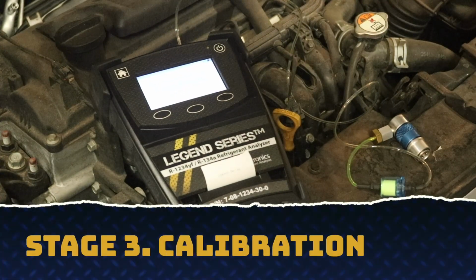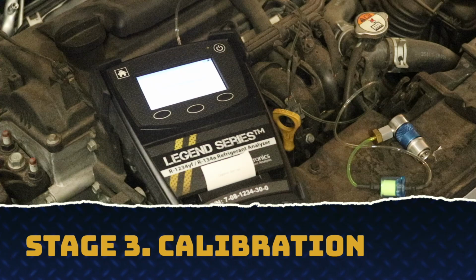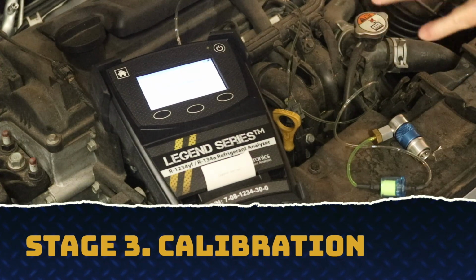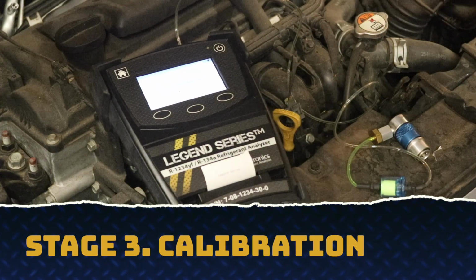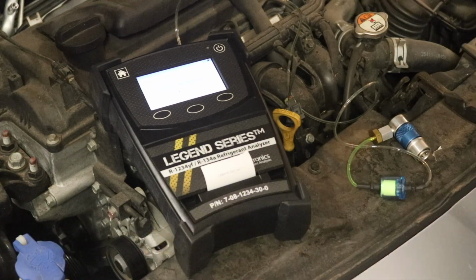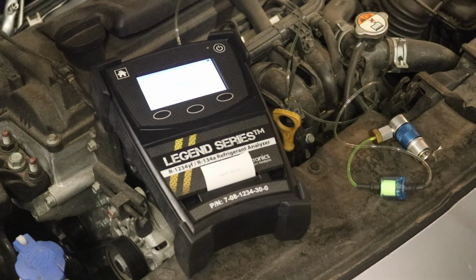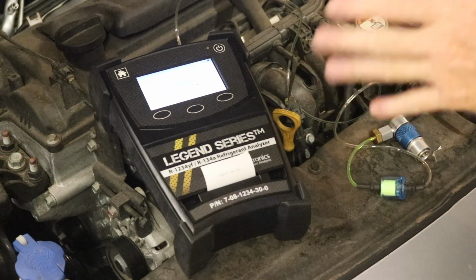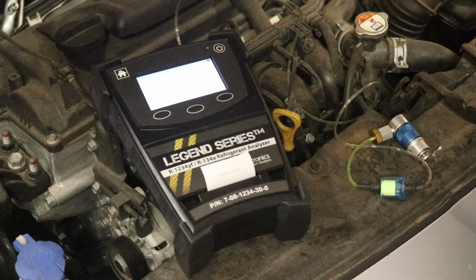And we're now in the third phase, or the calibration phase. You may hear the internal pump or purge motor running as it's going through the calibration. And the one thing I've learned over the years with any of these refrigerant analysis tools is to do the calibration in the vicinity of where you are testing the sample. Don't calibrate the tool in the safety of your air-conditioned office that's remote from the workshop. Calibrate it where you're going to do the sample, and you can be guaranteed of an accurate reading.